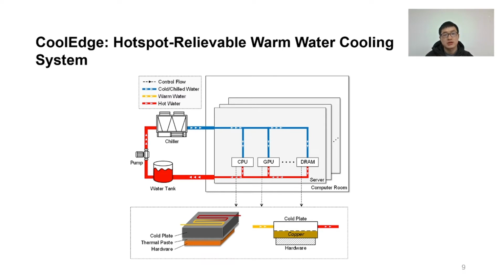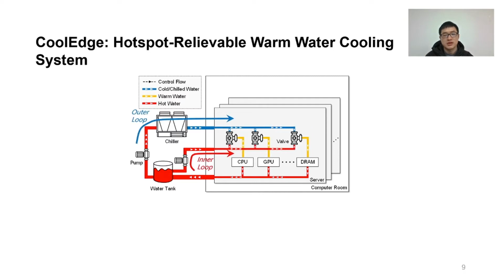To eliminate hotspots among different components, we redesign cooling loops named inner loop and outer loop that customize the water temperature and flow rate for each hardware component by mixing certain amounts of hot water directly from the water tank and cold water from the chiller through a valve.